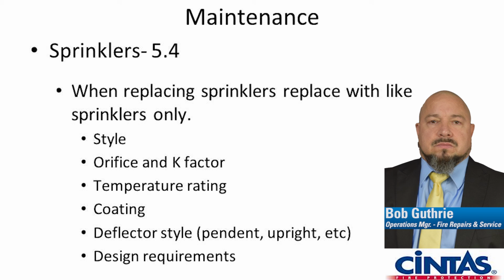So if it has a K factor of 5.6 and we replaced it with a K factor of 8.0, we have changed the design of that sprinkler system. That is something that we're not supposed to do. Temperature rating: if we take a 155 degree head out and all we've got on the truck is a 200 degree head, that is not a justifiable reason to change the temperature rating.